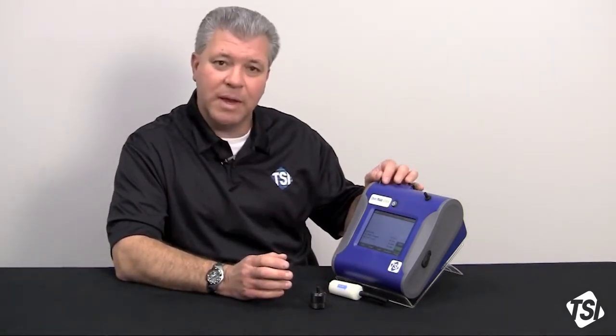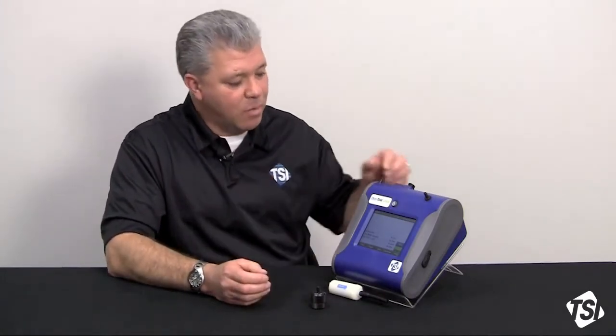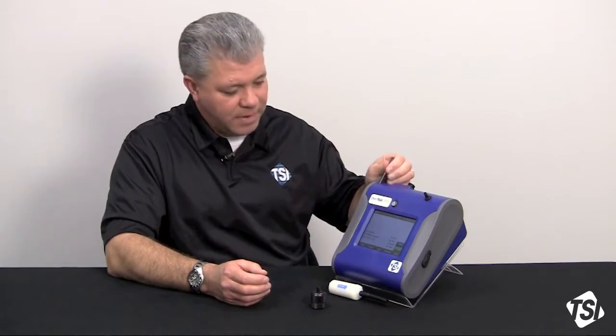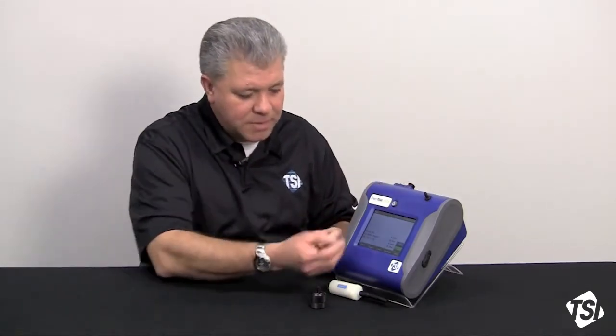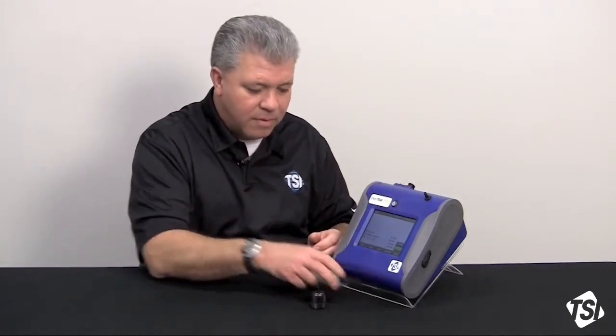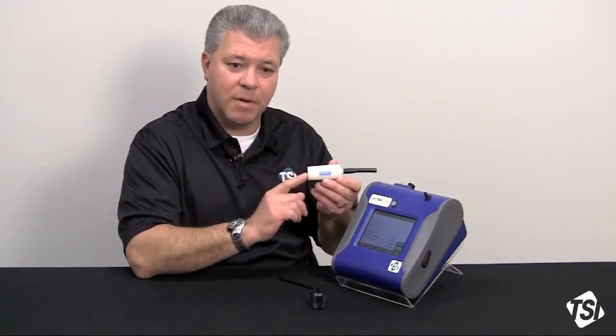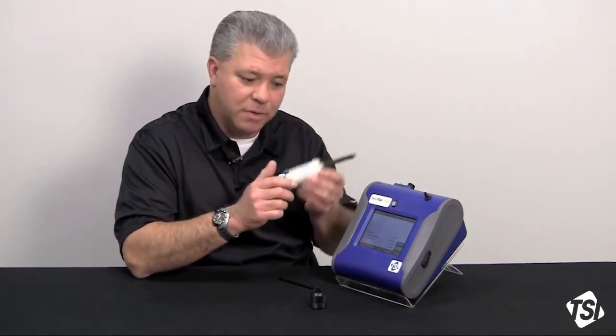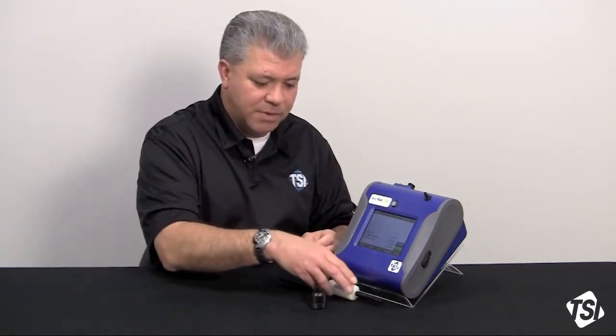Specifically, what we're going to be doing is looking at a change in the ambient aerosol size distribution to the size distribution of Arizona road dust, or A1 test dust, that the DustTrak is calibrated to. And how we're going to do this is very simple. We're on the main screen right now. We've also zeroed the instrument already. That's something that's critical to do before you do a size correction factor calibration in real time.